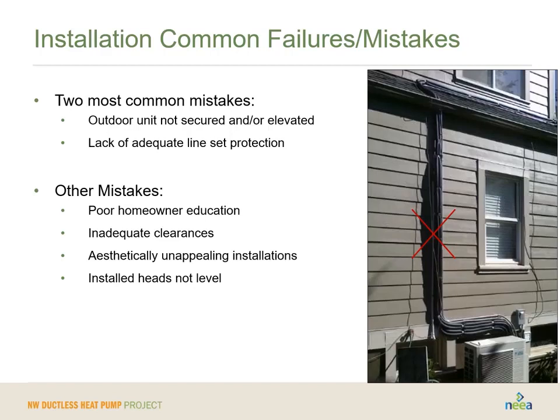The second big problem is lack of adequate line set protection. So what you see here, it is insulated, which is great, but this is not a UV proof insulation. So it either needs to be covered with a tape or some sort of sealant or hidden under a line set cover. That is really critical. Now, in this particular case, this is an outdoor unit, and you see there's a lot of different refrigerant lines. This is not your standard displacement, one indoor head, one outdoor head, and so that's probably why this installer did not use line set. He or she had too many refrigerant lines running simultaneously. So in this case, having a sealant, using the correct line set insulation, or putting a UV wrap over it would be preferred.